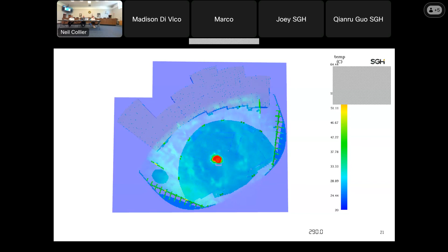Here we are 4.5 minutes into what we consider a conservative fire event. Temperatures on that seating rake and elsewhere are not getting too high, in degrees centigrade. So we determined that 4.5 minutes in, there's no heat problem at that highest elevation where people are. Heat is accumulating above the vented roof structure, but it hasn't gotten hot yet at 4.5 minutes. Now let's look at visibility, our other tenability criteria.